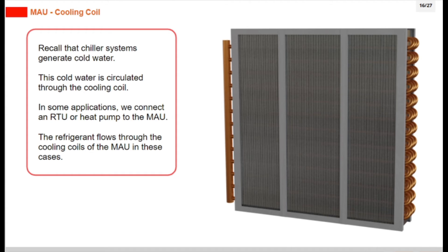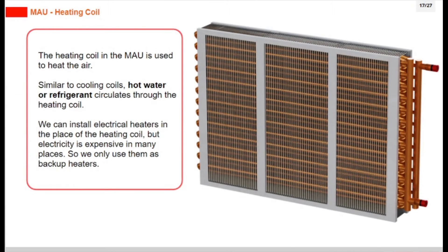The heating coil in the MAU is used to heat the air. Similar to cooling coils, hot water or refrigerant circulates through the heating coil. We can install electrical heaters in place of the heating coil, but electricity is expensive in many places, so we only use them as backup heaters.